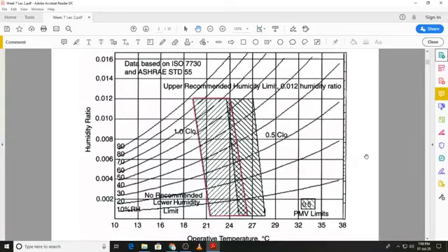Now we can look at the ASHRAE Standard 55, which is, as I said, a modified psychrometric chart. You can see the humidity ratio on the vertical axis on the left hand side. Instead of the dry bulb temperature, what you have is an operative temperature, and I'll come to the definition of operative temperature shortly. On the right hand side on the vertical axis, it's not shown over here, but we have the dew point temperature. Then you can see there are certain other numbers shown over here. Of course, you have the relative humidity, but two other numbers we can see: 1.0 CLO, and the other is 0.5 CLO.